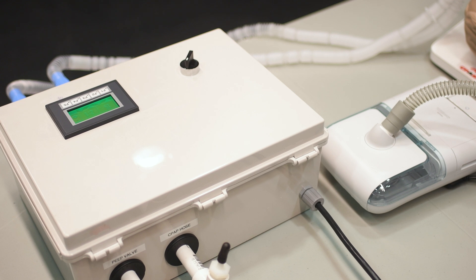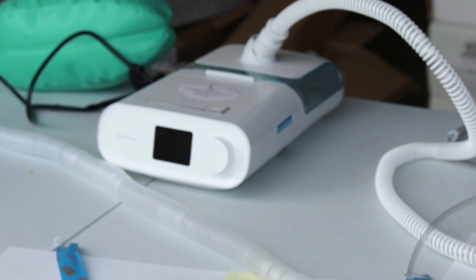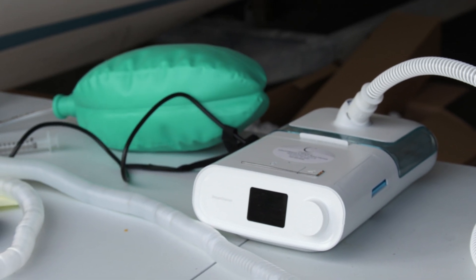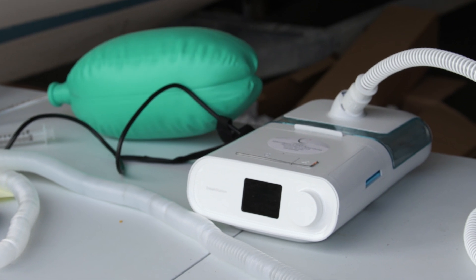Close that valve, then open an exhaust valve which allows the person to exhale to the atmosphere. One of the most important measures of what a ventilator is providing to the patient is the tidal volume — the amount of air that goes into and out of the lungs for every breath. Each patient may require a different tidal volume depending on their size or progression of disease. We ran a test varying all the parameters on the system, and the results showed that the tidal volume produced is consistent with what would be needed in a medical facility.